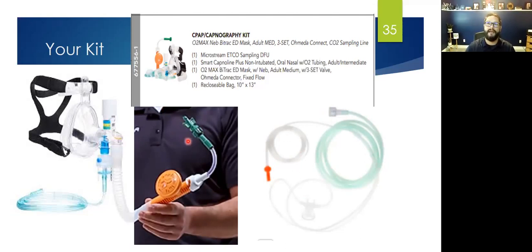The next thing is, you guys have one of two things right now. We're going to fix this. Right now, you're primarily using the little green spinny thing that goes on the DISS port. You're going to hook that up, and I'll show you that on the next slide a little deeper. But when we sell it to you, we also make sure it has this Ohmeda connection right on there. This Ohmeda connection will hook into a connection on your portal, which I'll show you in a second, but it will also hook into the wall of your ambulance and the wall of the hospital, so you can walk right in. Now this is important. You're going to see this on your next form of questions: this draws 15 liters a minute off your tank, off your oxygen source, and then through this filter right here, it entrains another 125 liters a minute. So 15 and 125 delivers approximately 140 liters a minute to the patient.